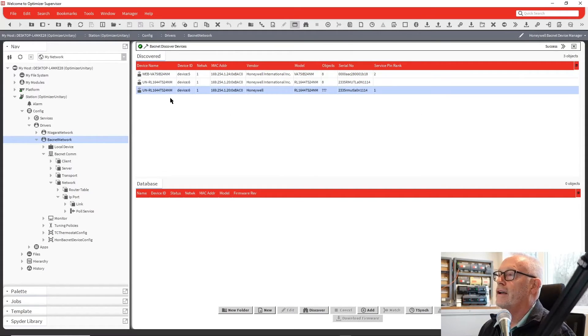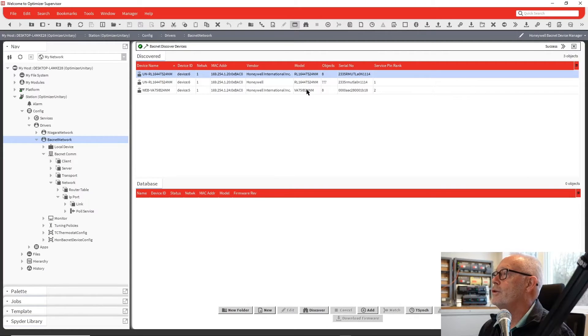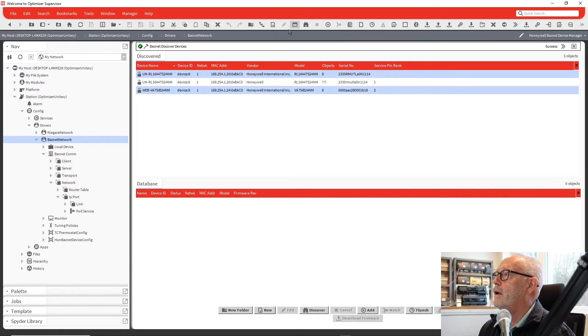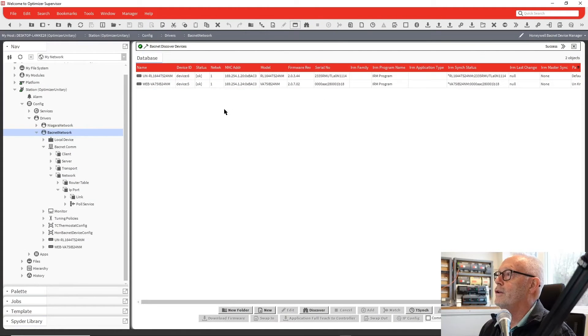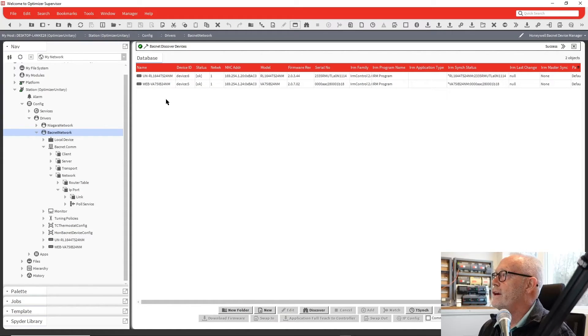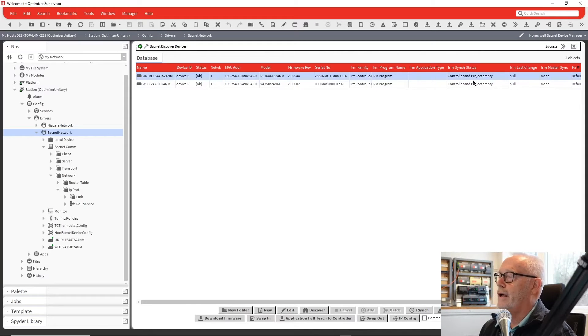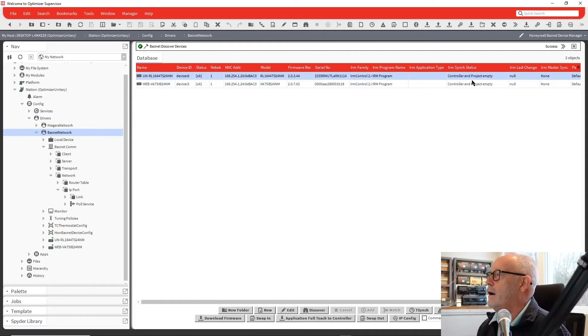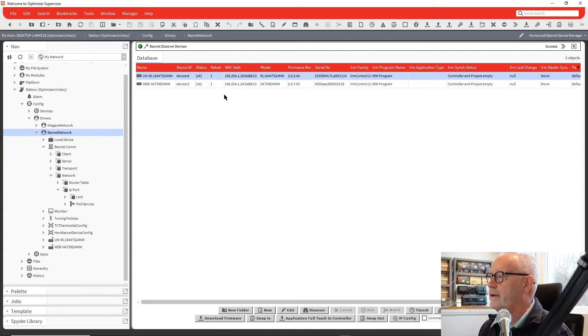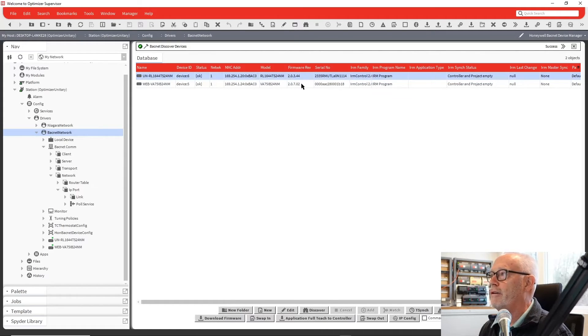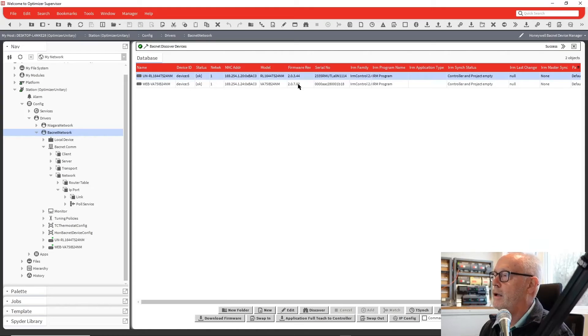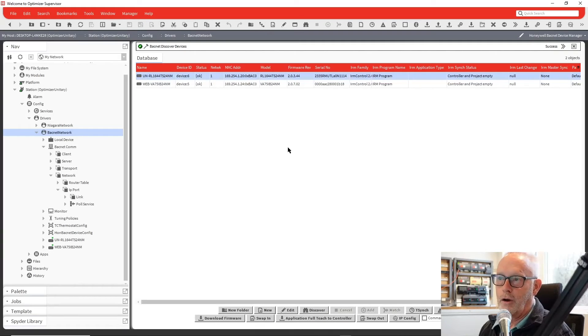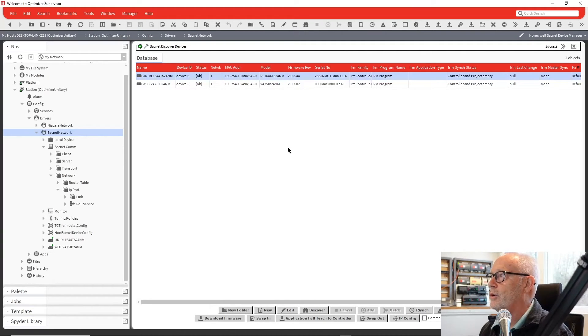So in this case, there's the service pin ranking for number one. I did press the unitary first, and there is my second one. So now if I come through here, I'll take the two controllers and I will drop them on my network. And then we can see now our two controllers are there. You see I don't have anything in the controller yet. I don't have an application in there. I just have the controllers brought in directly out of the box. One of the things you'd want to look at probably now is firmware revision. Make sure you're at the latest firmware. And if you're not, you're going to want to go and select the controller, go to download firmware, and pick the current firmware that's available, and get that set up in the controllers.